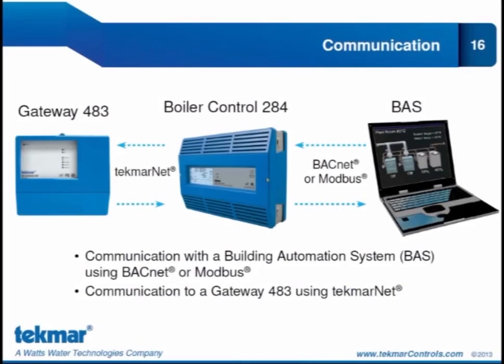The boiler control 284 can communicate with a building automation system using BACnet or Modbus, and can also communicate with a gateway 483 using tekmarNet communication. Remote monitoring and adjustment is possible through communication with the building automation system, and is also possible with the TN4 connection to the gateway 483.